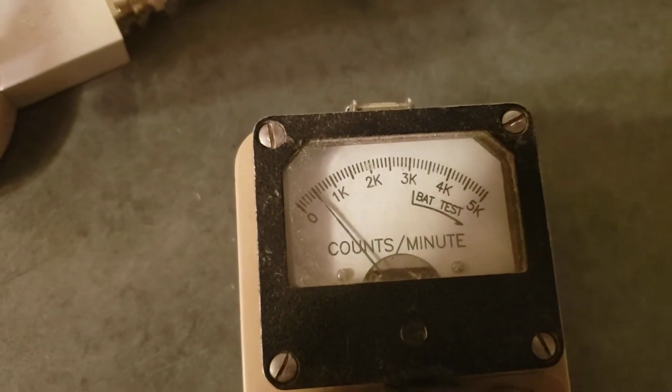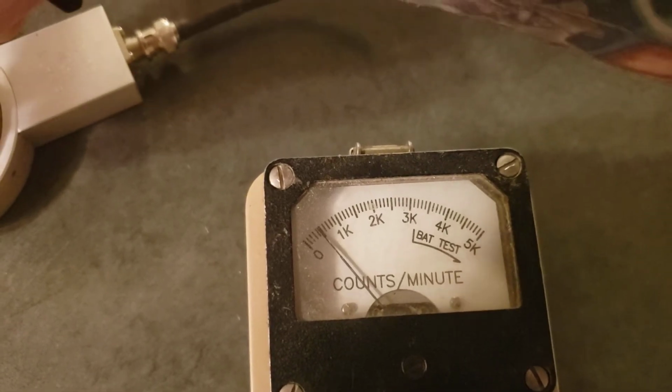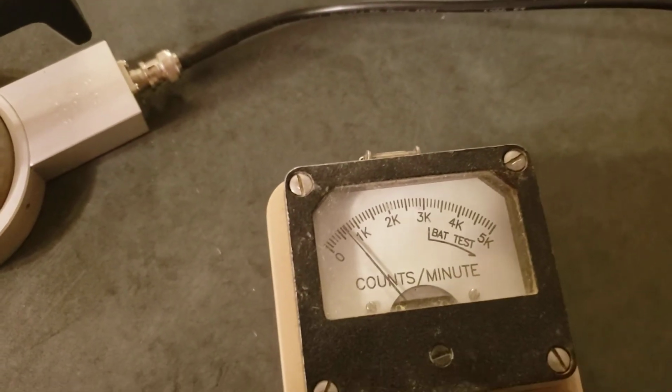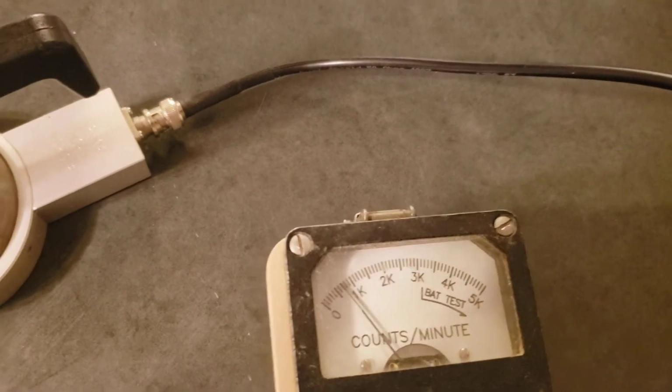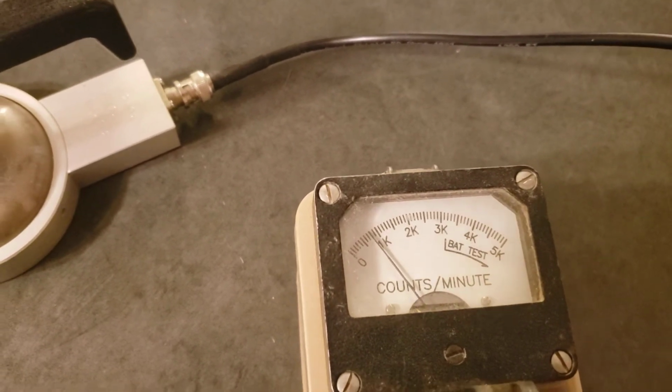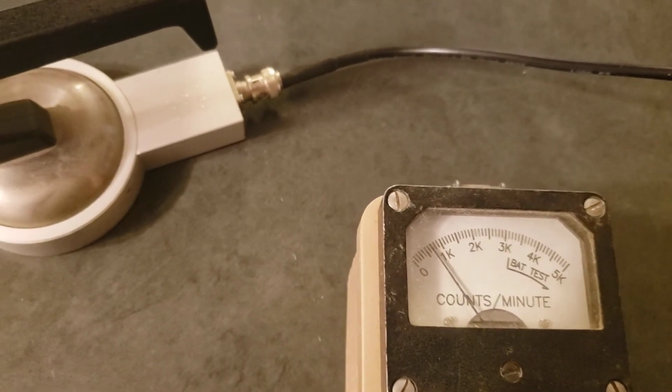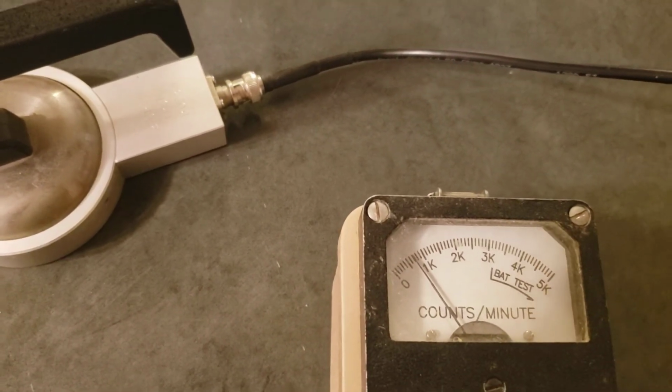Alrighty, so now what we have is an area that's been decontaminated. I mean, in the camera you can still see there's a speck here and there. But with our readings, we're not going to see consistently up in the range that we saw before of 200 counts per minute. What we're going to see is going to fall into what's called the NORM range, which is your regular normal background. NORM is an acronym. I'm not going to go into it right now. But what this is showing us is that we are not having that contamination that we had before.